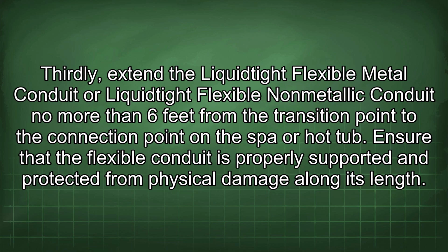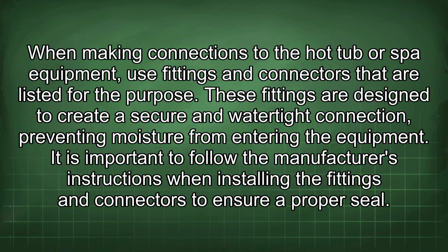Thirdly, extend the Liquidtight Flexible Metal Conduit or Liquidtight Flexible Nonmetallic Conduit no more than 6 feet from the transition point to a connection point on the spa or hot tub. Ensure that the flexible conduit is properly supported and protected from physical damage along its length. When making connections to the hot tub or spa equipment, use fittings and connectors that are listed for the purpose. These fittings are designed to create a secure and watertight connection, preventing moisture from entering the equipment. It is important to follow the manufacturer's instructions when installing the fittings and connectors to ensure a proper seal.